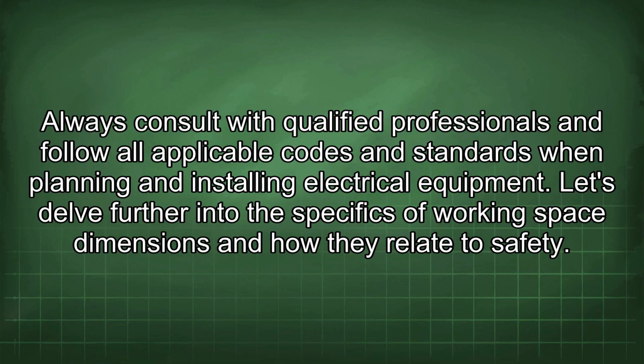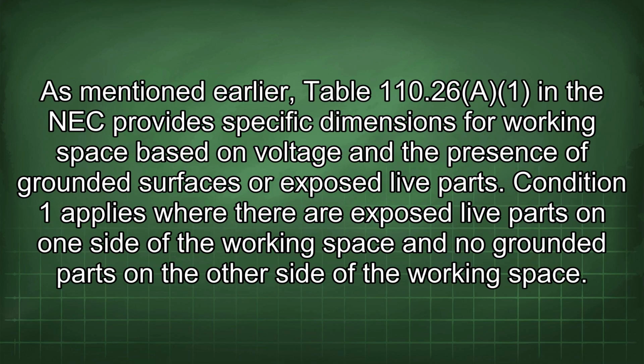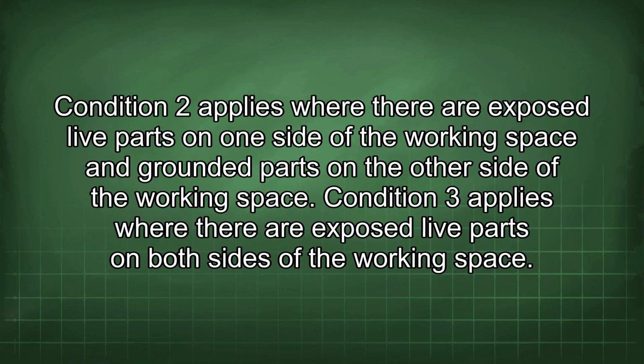Let's delve further into the specifics of working space dimensions and how they relate to safety. As mentioned earlier, Table 110.26(A) in the NEC provides specific dimensions for working space based on voltage and the presence of grounded surfaces or exposed live parts. Condition 1 applies where there are exposed live parts on one side of the working space and no grounded parts on the other side of the working space. Condition 2 applies where there are exposed live parts on one side of the working space and grounded parts on the other side of the working space.